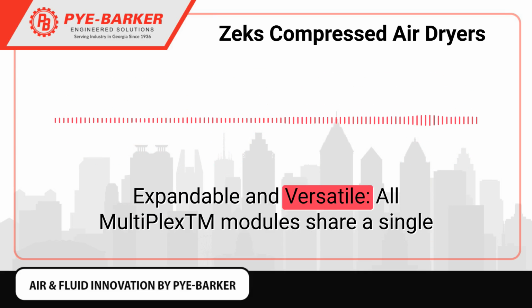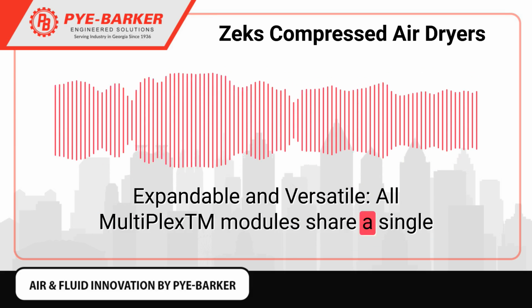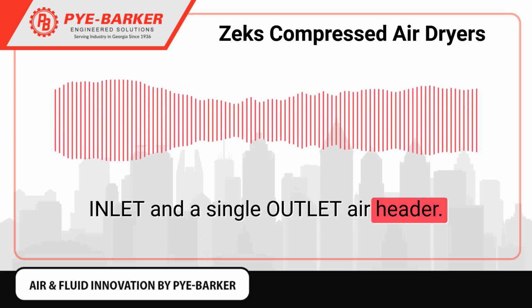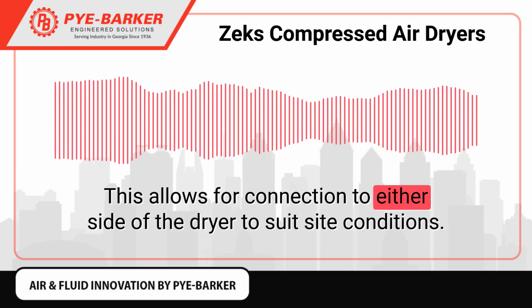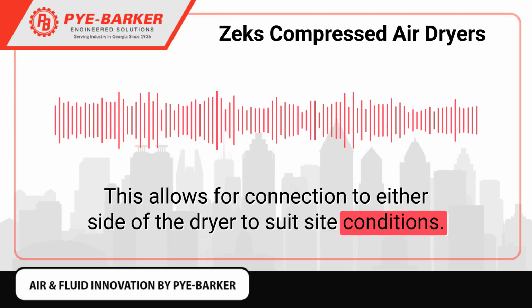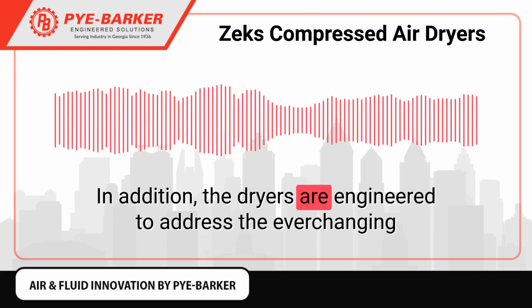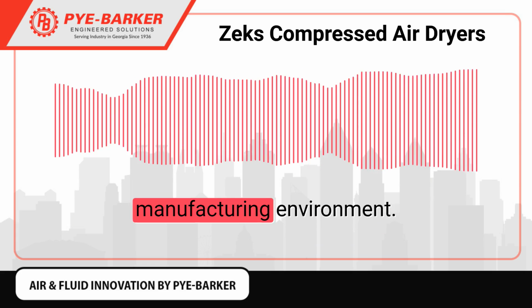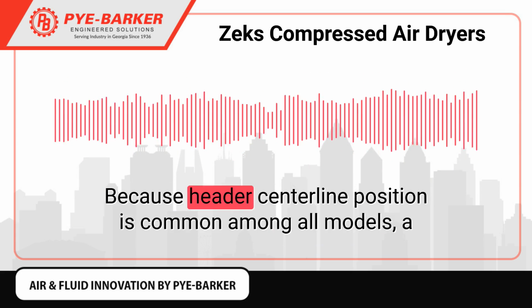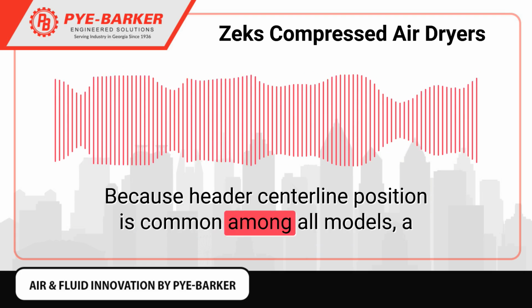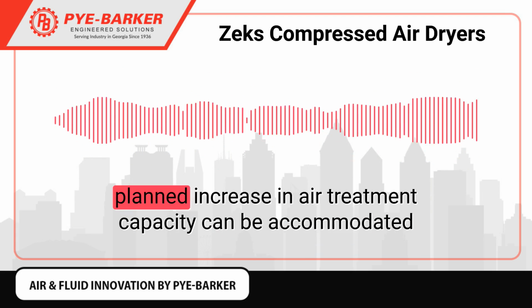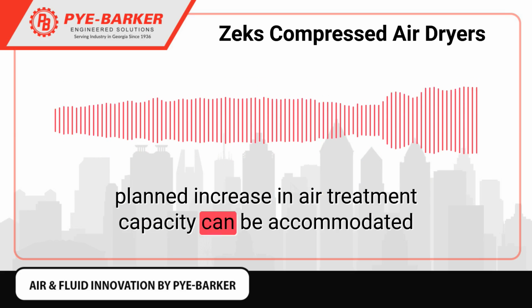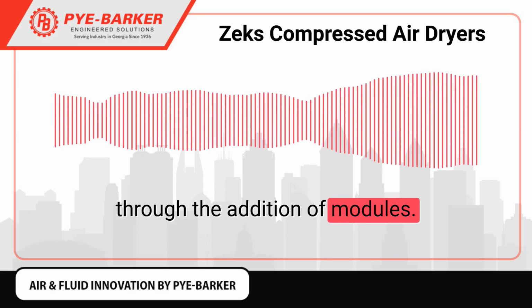Expandable and versatile. All MultiPlex™ modules share a single inlet and a single outlet air header. This allows for connection to either side of the dryer to suit site conditions. In addition, the dryers are engineered to address the ever-changing manufacturing environment, because header centerline position is common among all models. A planned increase in air treatment capacity can be accommodated through the addition of modules.